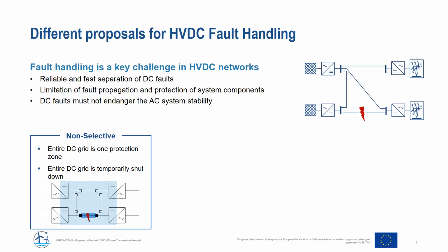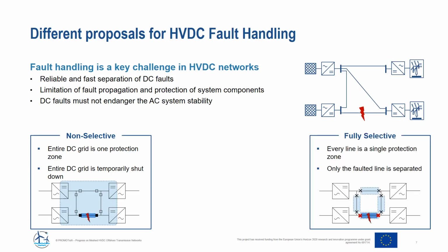What's presented here are the strategies according to the grid definition. The first is the non-selective strategy, where the entire DC grid is one protection zone, so the entire DC grid is temporarily shut down and de-energized during the fault clearing process. The second option is fully selective fault clearing strategies, where every line is a single protection zone. So each line is separated by DC circuit breakers at each line end, which is very similar to the current protection design in AC systems.